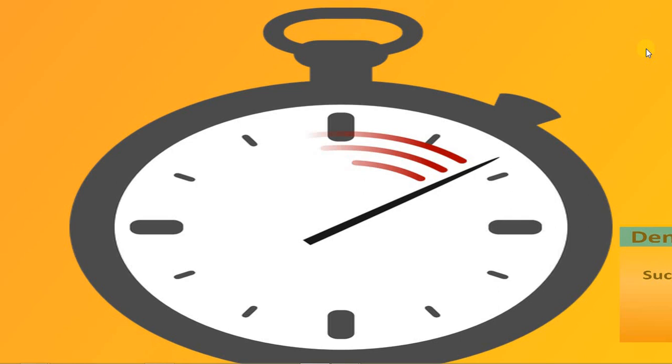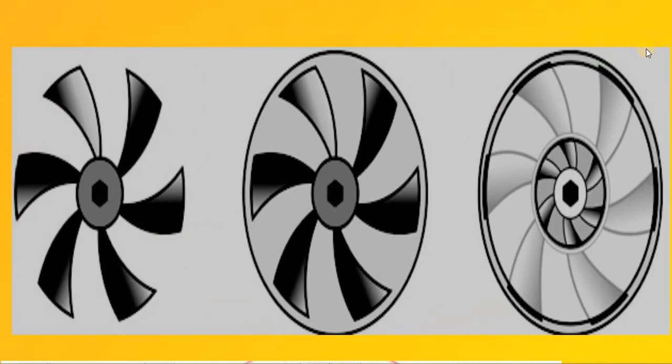During the inertial rotation, the impeller works like an exhaust fan and draws outside air through the exhaust tubing into the turbine handpiece as well as into the treatment unit. This is called the Suckback Phenomenon.